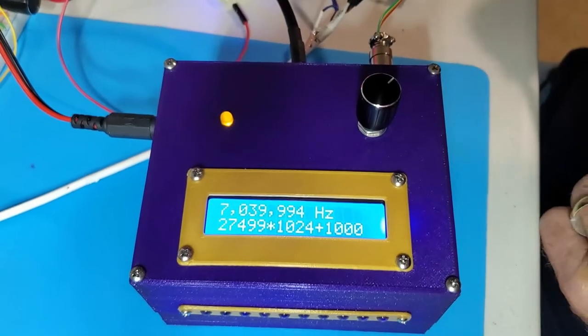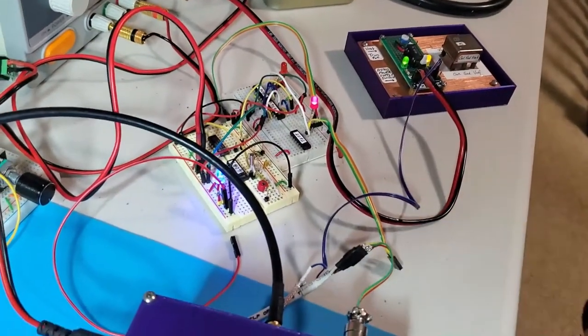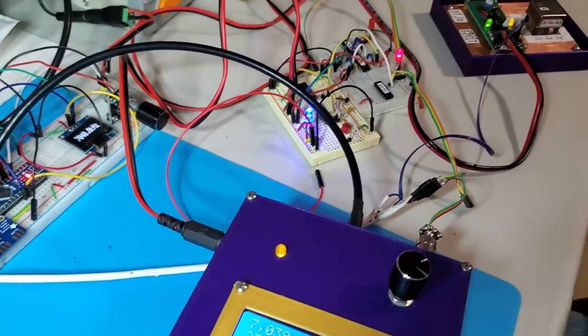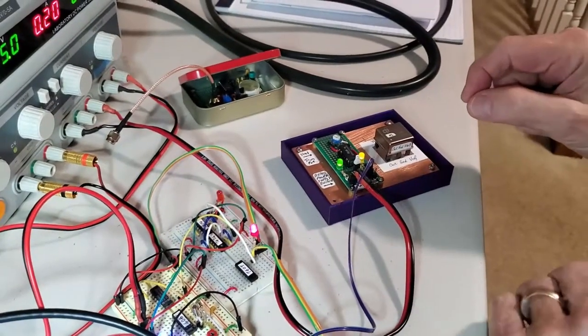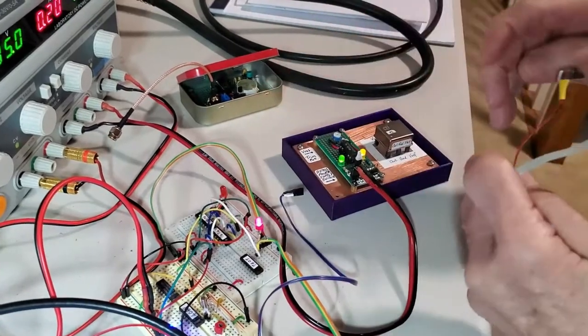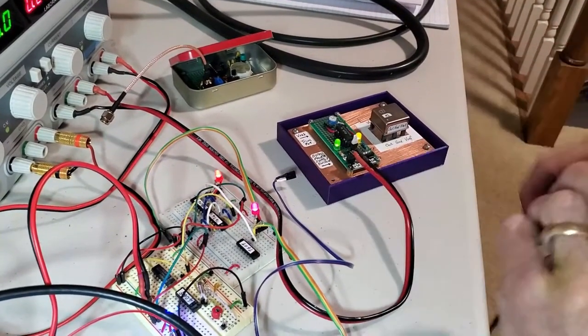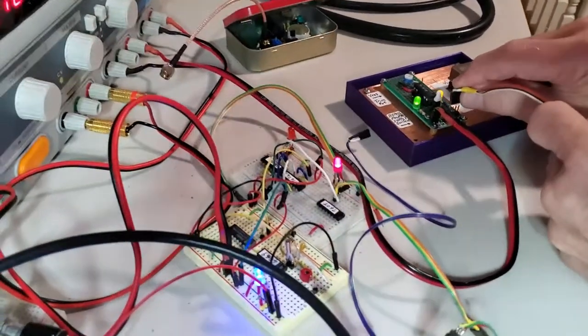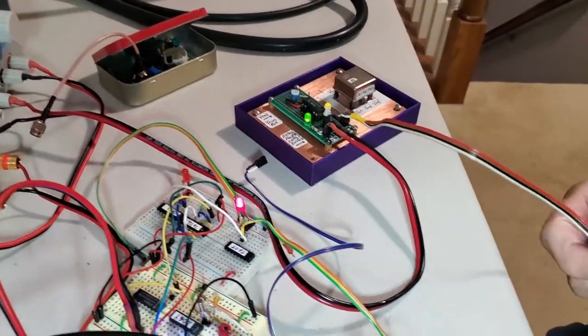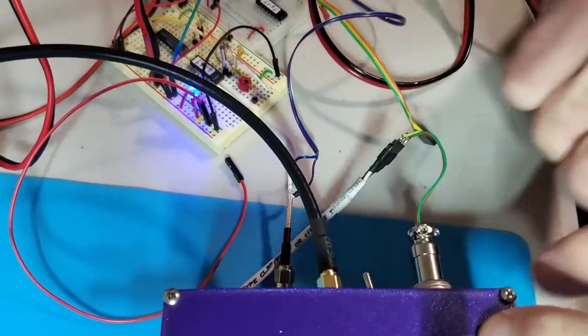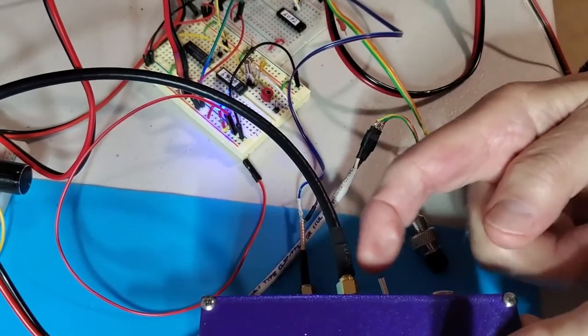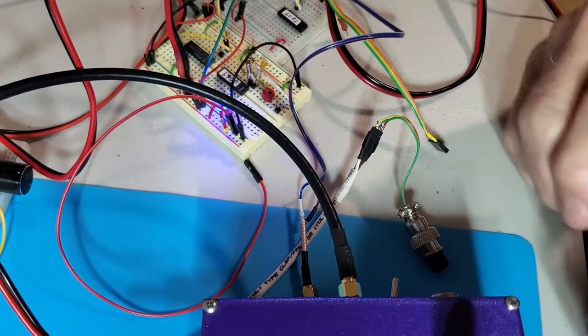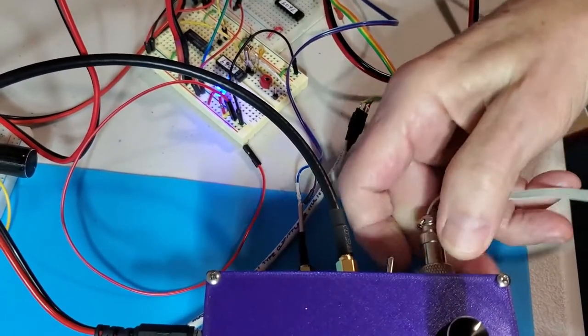Now what I want to do is disconnect the GPS and substitute this OCXO. So let me unplug the output from the OCXO and use this adapter right here to connect it to the frequency counter's time base input. We'll unplug the GPS and we'll flip this to 10 megahertz. The toggle switch was in the one hertz position and now it's in the 10 megahertz position.